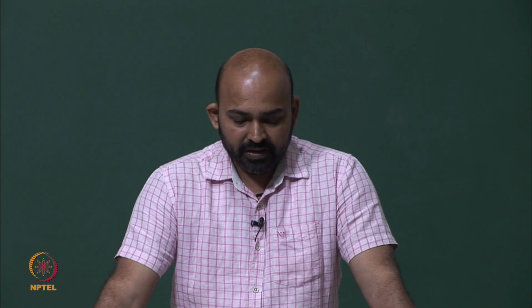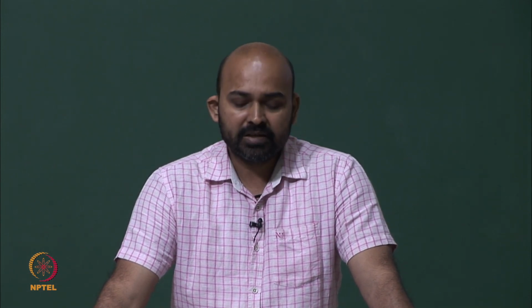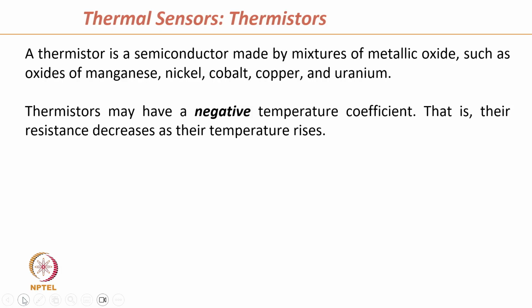So, after this we come to the third type of thermal sensor, which is thermistors. A thermistor is a semiconductor made by a mixture of metallic oxides such as oxides of manganese, nickel, cobalt, copper and uranium. So, unlike the RTD, it is a mixture. In the RTD we discussed a pure metal which has resistance proportional to temperature. A thermistor is not a pure metal, it is a mixture, and depending upon what you mix, you can have more than two materials to mix with. Depending upon the mixture and its contents, the output characteristic of the thermistor changes.